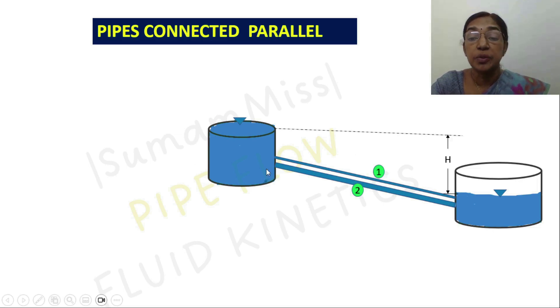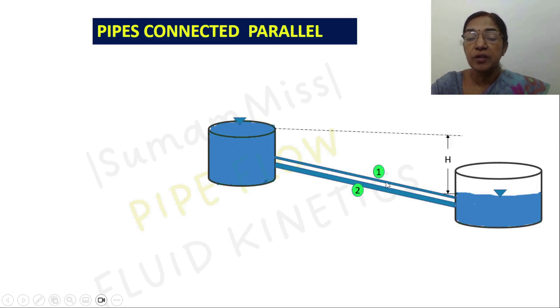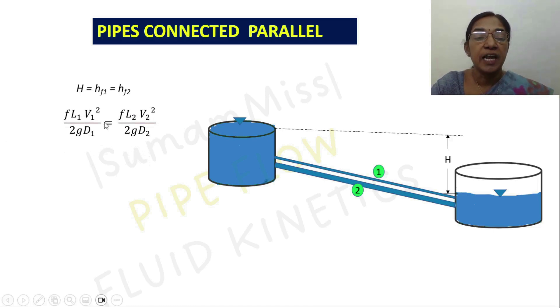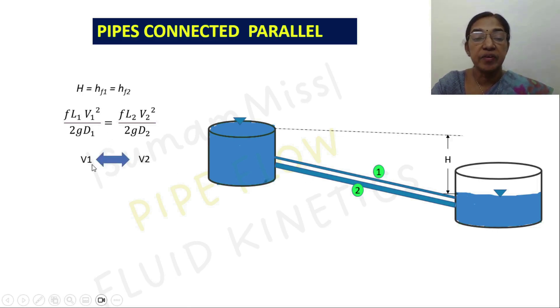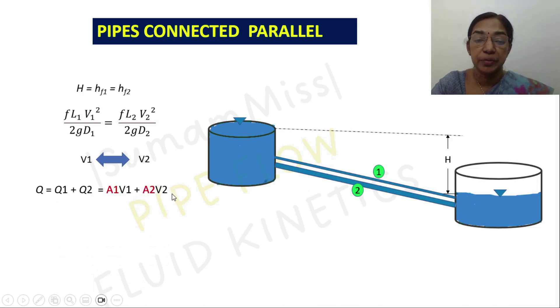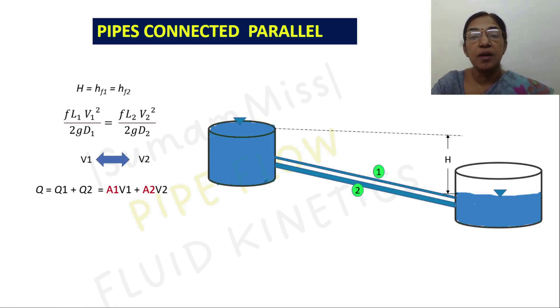Similarly, we can connect pipes in parallel to increase the discharge. Here you can see two pipes connected in parallel connecting two tanks. The difference in liquid level in the two tanks equals h. This means the head loss for pipe section 1 equals the head loss for pipe section 2 equals h. So fL1V1²/(2gD1) = fL2V2²/(2gD2). If the same material and known diameters are used, we establish a relationship between V1 and V2. The total discharge Q = Q1 + Q2 = A1V1 + A2V2. From the relationship between V1 and V2, we can express Q in terms of either velocity, then find each discharge component.